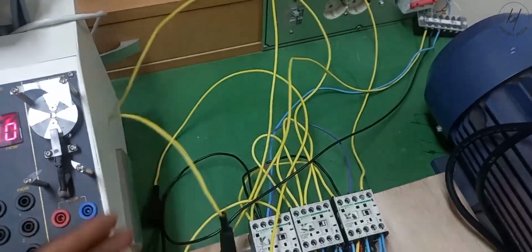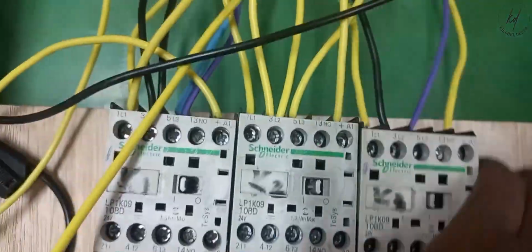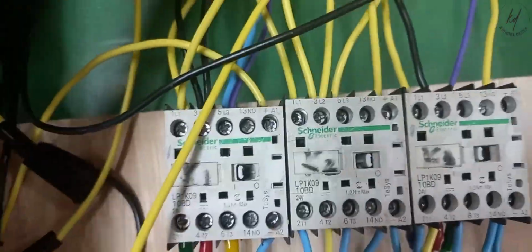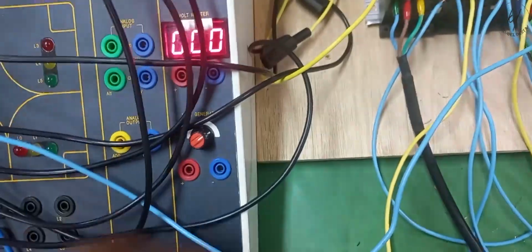There are mainly 4 states in a star delta starter. First, off state. This is the off state of the starter, all the contactors are in the off position. Second, star state. In this state, main and star contactors are closed and the delta contactor is open. The motor is connected in star.